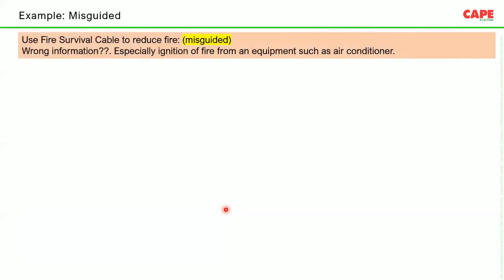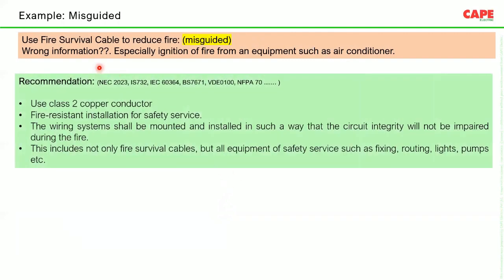Another misguided idea is, sometimes, that fire survival cable can reduce fire. For example, in one report I have seen, there was an air conditioner fire, and the report says all wires should be fire survivable. Actually, this is again not the correct information. The fire started from the air conditioner. Even if you use a fire survival wire, the problem is in the air conditioner, not in the wire. The recommendations in the standard say you should use class 2 copper conductor. Fire resistant installation for safety services is mandatory. The wiring system shall be mounted and installed in such a way that circuit integrity will not be impaired during fire, and so on.